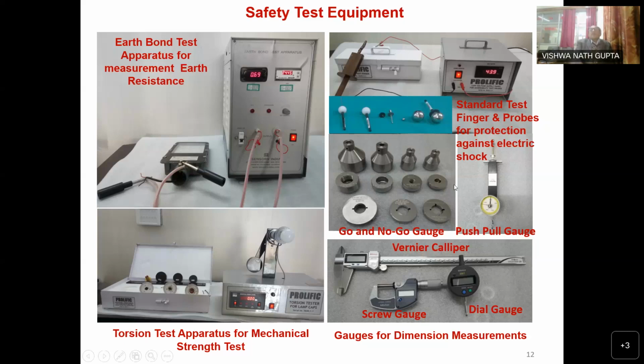So these are the standard fingers, sir. Same thing, I told you, the ingress protection of solid objects. These are used first, like the dust chamber, which is used for the measurement of particles and dust. If we say an outer body is IP21 or IP31, these instruments are used to determine the first degree of the ingress protection. This is the torsion test apparatus for mechanical strength tests, along with gauges for dimensional measurements.